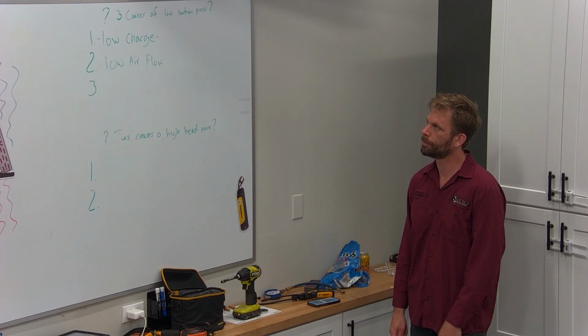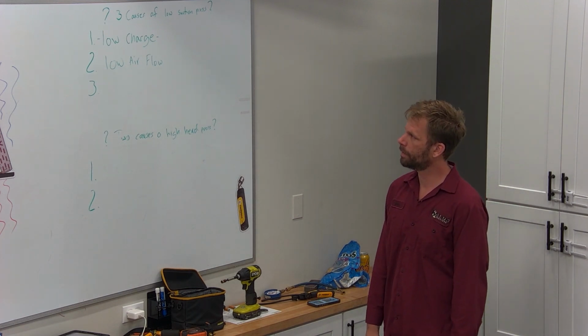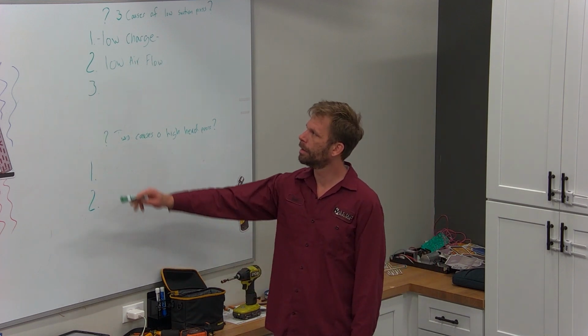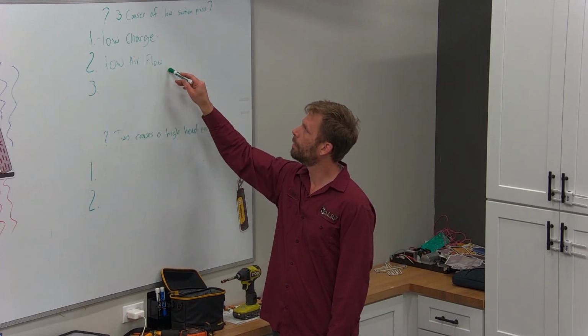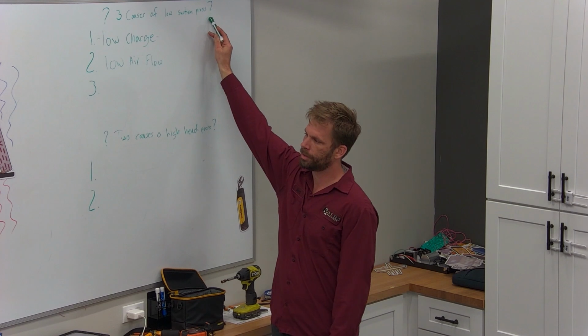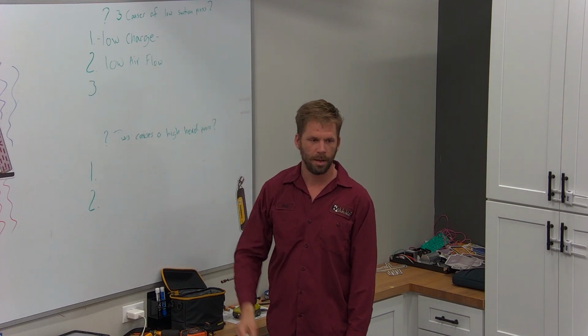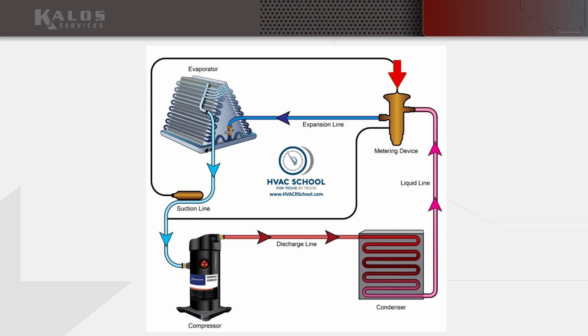Low airflow. Now, before I move to the third one, how in the heck does low airflow create low suction? That's what I mean, think about that. We got our pressure drop happening right here. The metering device is controlling our pressure drop. Our compressor is pumping it. Those two things don't change their function.